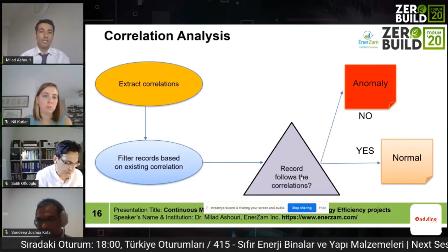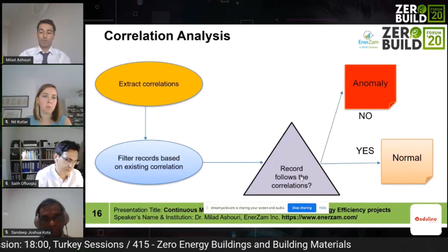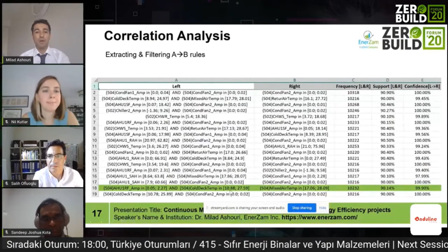About correlation analysis: we try to extract correlations among variables, and whenever the records show a correlation is violated, we flag it as an anomaly. Let me give an example. This data on the left comes from a real building. There are a lot of data points coming from the BMS, and depending on the complexity of the building, there can be up to 20,000 points — for example, condenser fan amp, mixed air temperature, chiller ampere, and more. We feed these variables into our engine and try to find correlations among them, and whenever these correlations are violated, it means something is happening in the data.